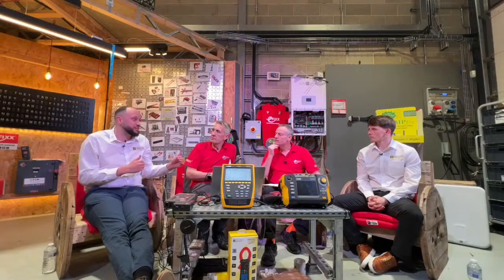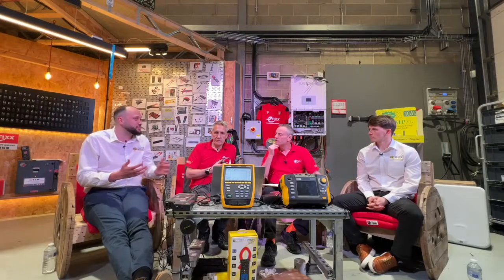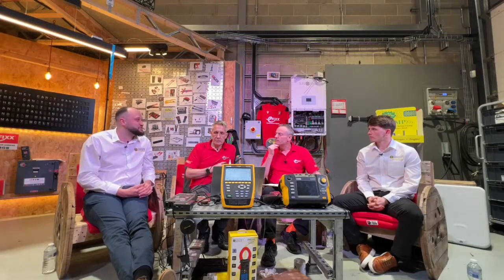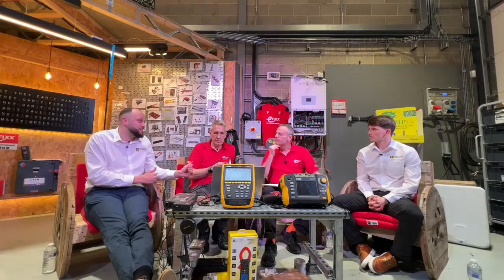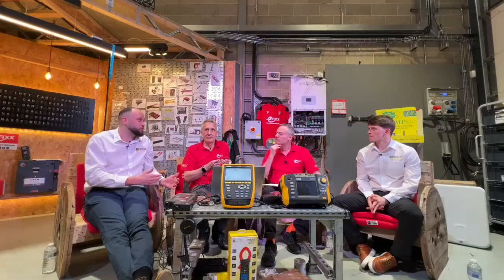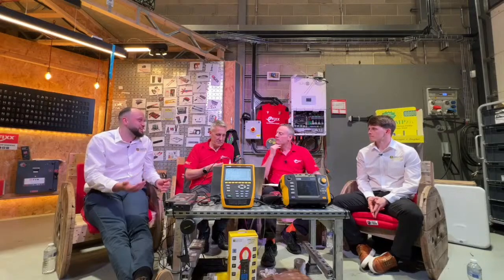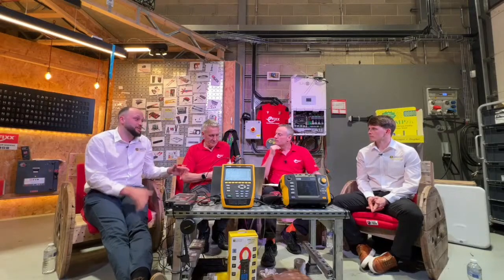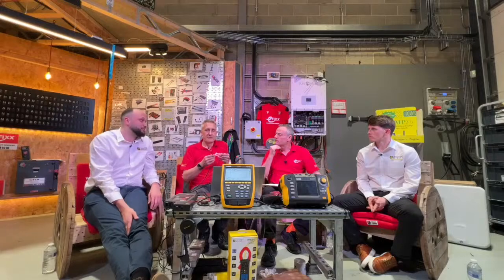Not only that, because it measures up to the 50th order, you can identify equipment that's not running efficiently, or isolate that after the fact. If you've got a 3-phase incomer attached and you're logging over a period of time, you can see a THD value for current, and then isolate what is causing that in most instances.